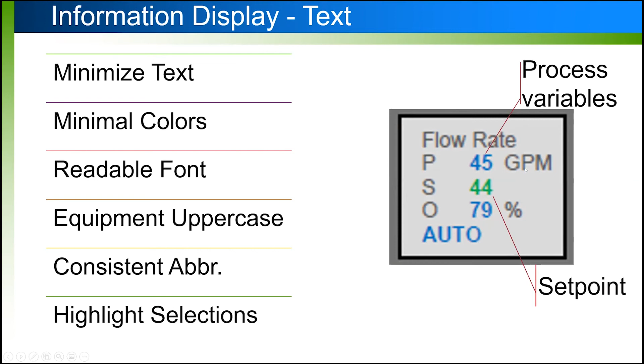When using abbreviations, you want to keep them constant. One thing we like to do is create a dictionary for each client, so we use the acronyms they use and display information consistently every time, so operators don't get confused. For example, if this screen uses GPM all uppercase, every time you use GPM you must use it in the same case, whether upper or lowercase.